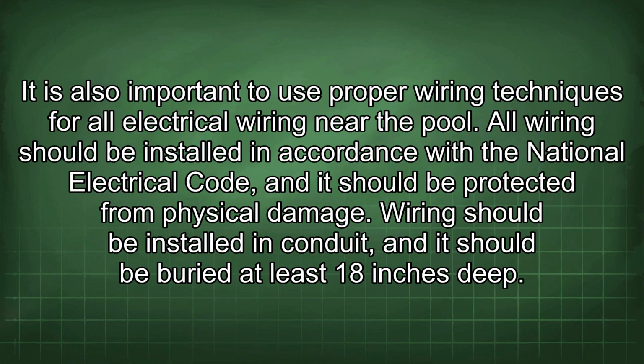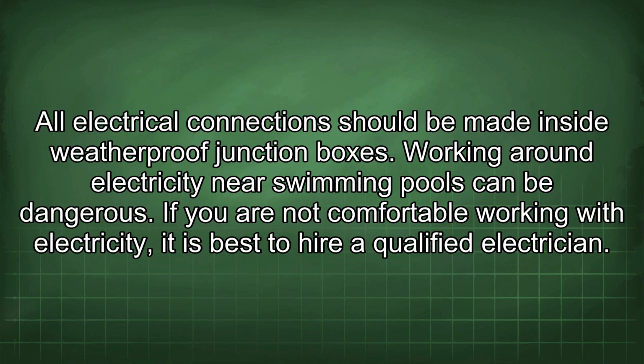It is also important to use proper wiring techniques for all electrical wiring near the pool. All wiring should be installed in accordance with the National Electrical Code, and it should be protected from physical damage. Wiring should be installed in conduit, and it should be buried at least 18 inches deep. All electrical connections should be made inside weatherproof junction boxes.